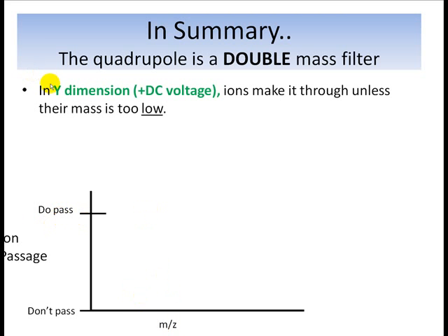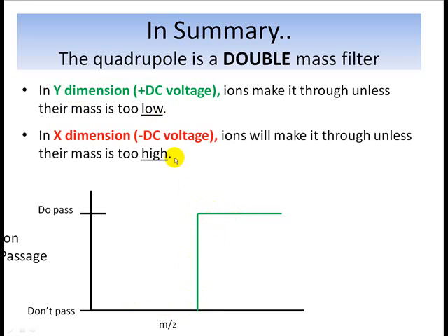So in the y dimension, to summarize, which has a positive DC voltage on those rods, the ions make it through unless their mass is too low. This is a little depiction of what the filter function is like for those y dimension electrodes. High like this means that they do pass. Low means that they don't pass. Some critical value of mass charge ratio above which it will make it through, but below that it won't.